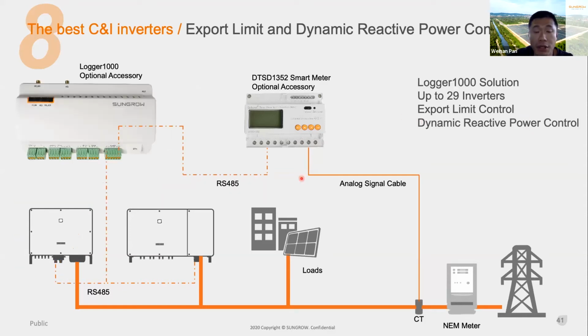And what if the project size is 1 megawatt or up to 30 megawatt, with more than 10 inverters installed? We will suggest you use our Logger1000, which is the optional accessory. The Logger1000 supports up to 29 inverters, which means a single Logger1000 can support a 3 megawatt C&I project. And as simple as that, you only need to connect one master inverter with the Logger1000 and then daisy chain the rest of them. It's simple and easy to do the export limit and the dynamic reactive power control.